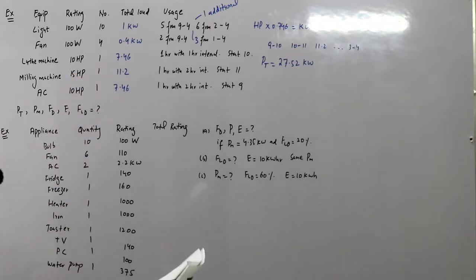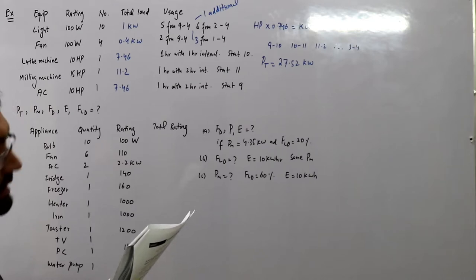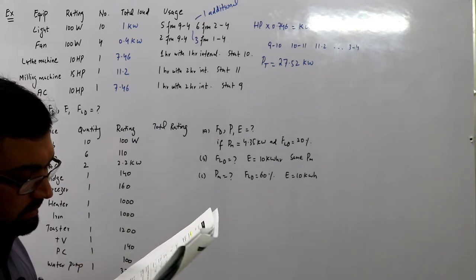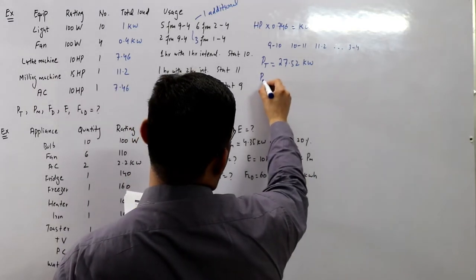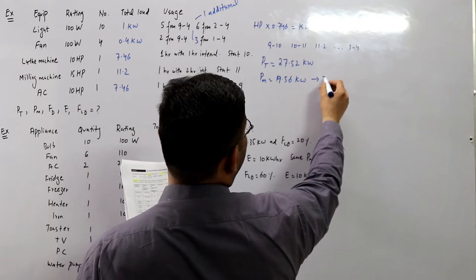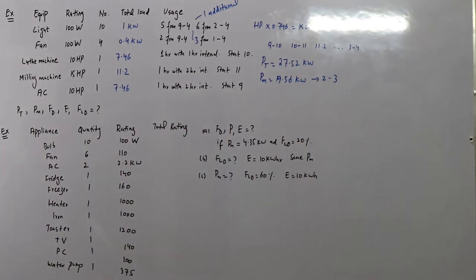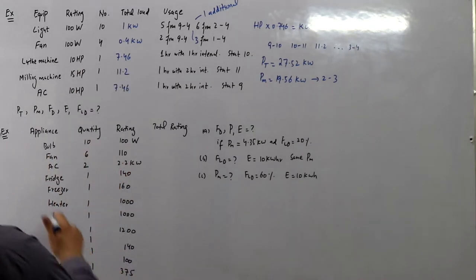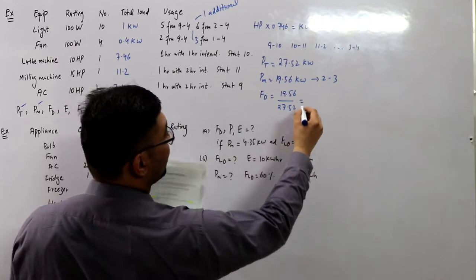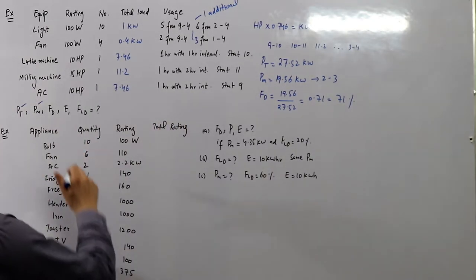The maximum demand is found on an hourly basis. The maximum demand is 19.56 kW, occurring between 2 to 3. This was seen in the previous video example. The demand factor fd = pm / pt = 19.56 / 27.52, which equals 0.71, or 71 percent.